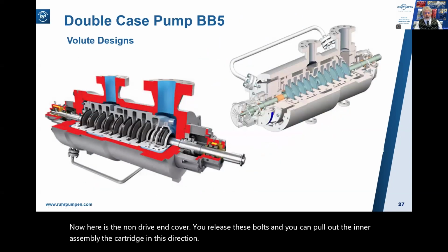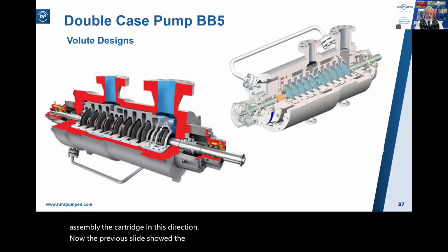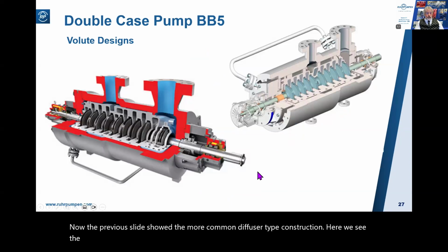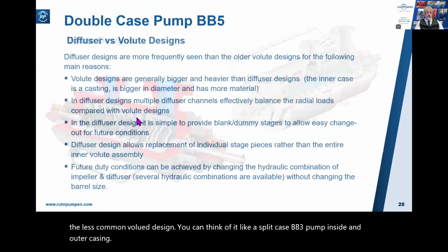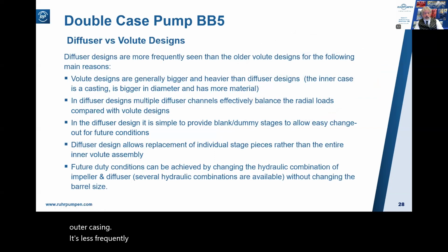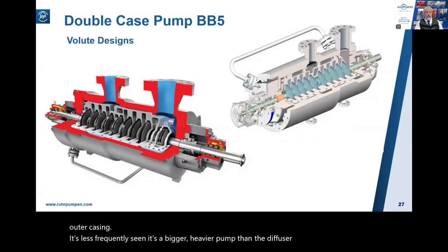Now, the previous slide showed the more common diffuser type construction. Here we see the less common volute design. You can think of it like a split case BB3 pump inside an outer casing. It's less frequently seen. It's a bigger, heavier pump than the diffuser design because the volute case is bigger.